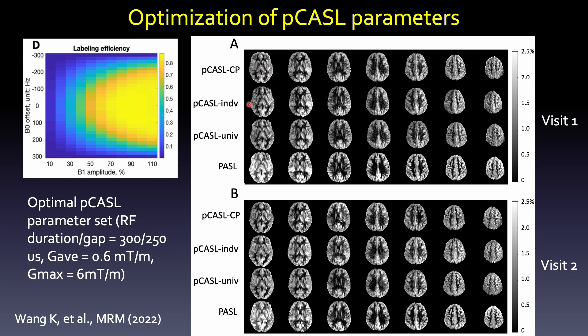And on top of that, you can use PTX pulse — PTX B1 shimming — to push up signal by 10%. And if you don't want to do individual calibration, you can use average B1 shimming, which we call universal shimming, to improve the signal slightly by 5%. Overall, all three conditions perform really well for PASL with good test-retest reliability. The bottom row shows PASL images acquired using the WURST pulse.